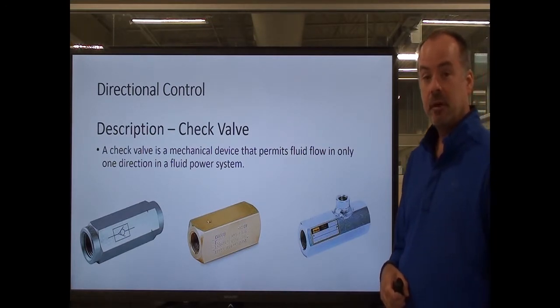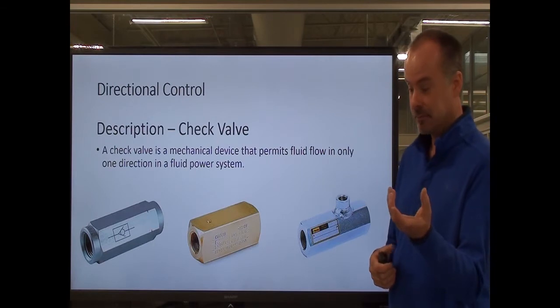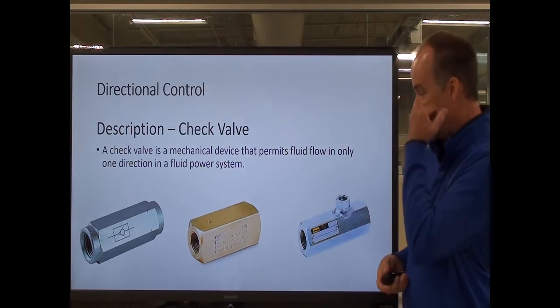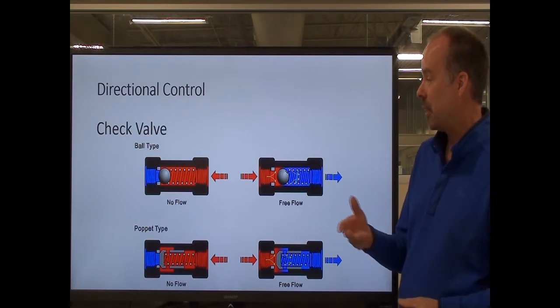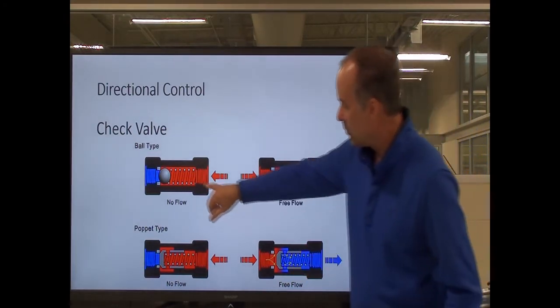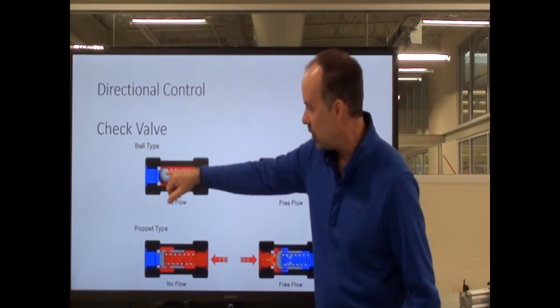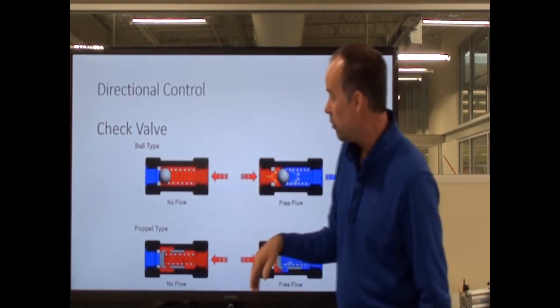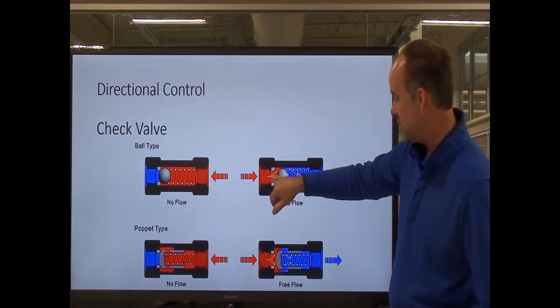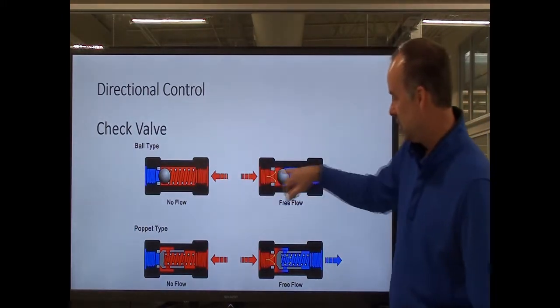Basically, a check valve allows fluid flow in one direction. If I've got a circuit or a place for fluid to flow, it'll allow it to flow in one direction but won't allow it to flow back. I've got two different types illustrated here: a ball type and a poppet type. With the ball type, I've got a ball that seals on a seat. When the fluid tries to go one way, it actually pushes the ball into that seat and seals it off. When I push fluid the other way, it pushes the ball off the seat against the spring and allows fluid to flow.